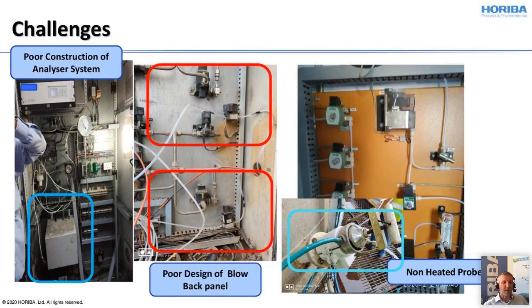Again, challenges, as mentioned before. You see here on the left, the installation is not well done. There is a poor construction of the full system. Then the next one, there might be a good engineering and a good construction of the basic system, but later on it was necessary to modify it, and this modification was not done properly on a blowback panel. And finally, in the third picture on the right hand, you see that there is a non-heated probe. It is directly connected to the sample gas, and this might clog the sample line, and you can't bring any gas to the analyzer.